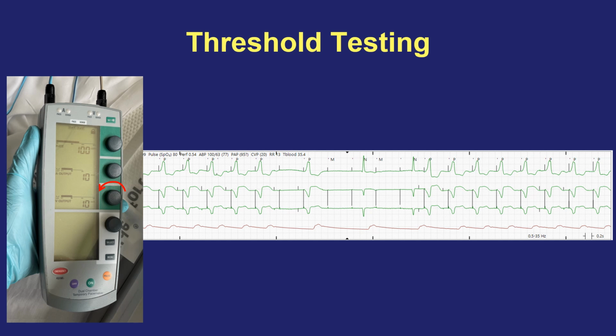And so it's important to know if this number is going up, and now their pacing threshold on postoperative day 4 is now 12 and then 14. There's a maximum amount of energy that this temporary pacemaker box can deliver, and if you're approaching that, then you're soon going to run out of room and no longer be able to capture the myocardium. And if the patient is still reliant on pacing, then one needs to anticipate that timing and figure out a different solution for temporary or permanent pacing.